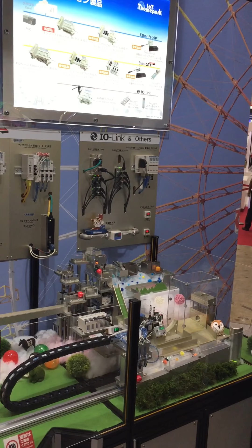So if you have a client building a machine, and he sells it to several customers who want Allen Bradley, EtherCAT, or Siemens, all your client has to do is change the master. Everything after that's the same. Their whole bill of materials will be identical, but the master for Allen Bradley will change, the master for EtherCAT will change. They just change the master, and all the components on the machine are the same, inputs and outputs, it doesn't matter. It makes it very simple for them to build a machine, and simple for a plant that's trying to improve productivity because they can diagnose it. One of the big problems with some of the older protocols is they can't diagnose it properly. With IO-Link, it's fully diagnosable.